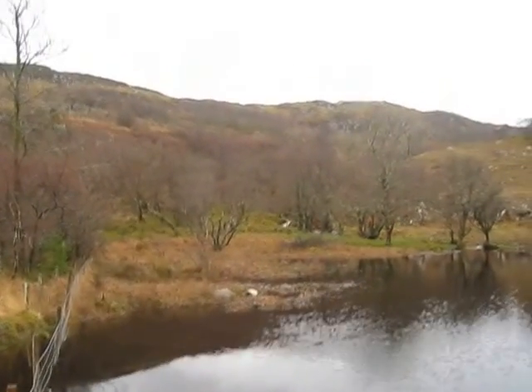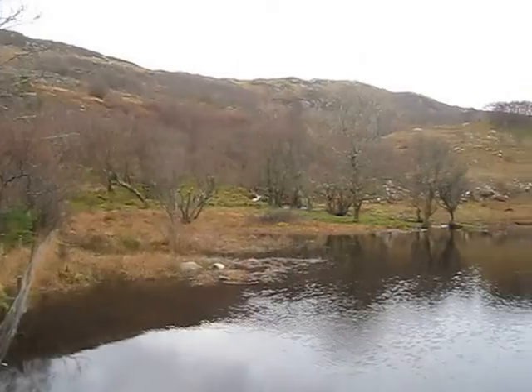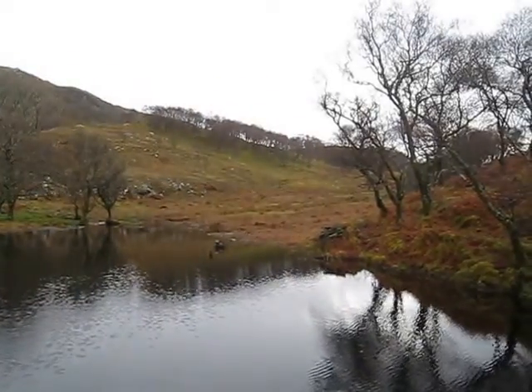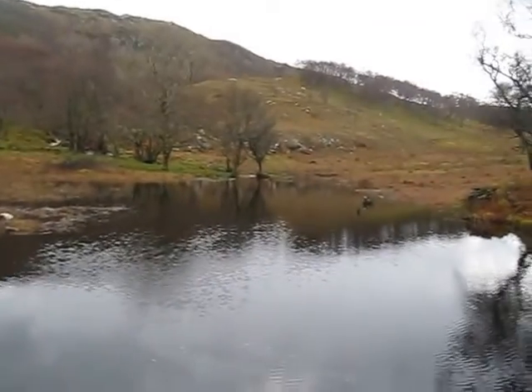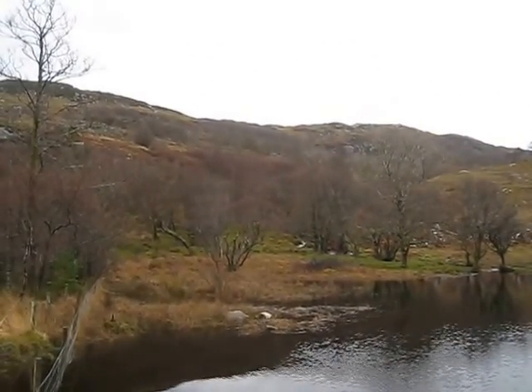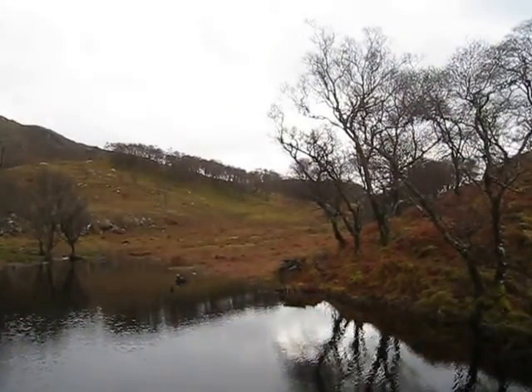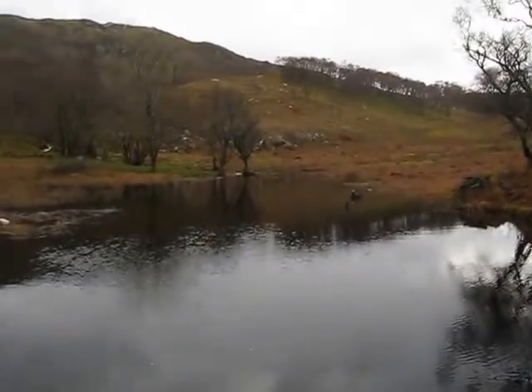The reason I chose this place to build the pond is because it goes up quite steeply behind. You'd say you should go higher up the hill, but off in that direction is a fairly major part of the catchment area. So if I'd bothered taking the pipeline further up to get the extra head up there, I'd have lost all the catchment area over here. So I decided to put the intake here, which only gave us 40 meters of head.